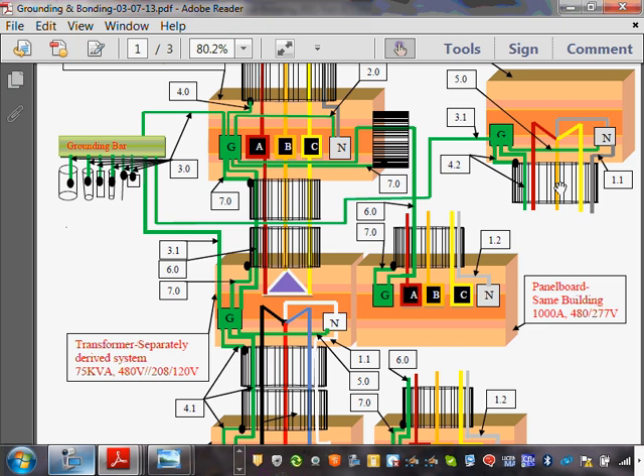Can I emphasize the word is, where is your circuit breaker? Does the generator have a circuit breaker on it, like a lot of generators do? They have a circuit breaker right there. When you pull the feeder out of that circuit breaker, then you are dealing with an equipment grounding conductor, and you size it based on the circuit breaker. So my circuit breaker here, the 2000 amp, is right at the generator. Then I will size the conductor based on 2000 amp.